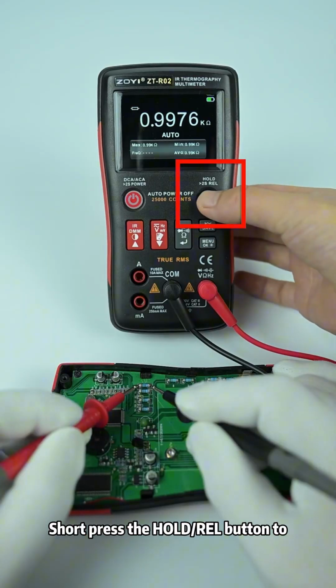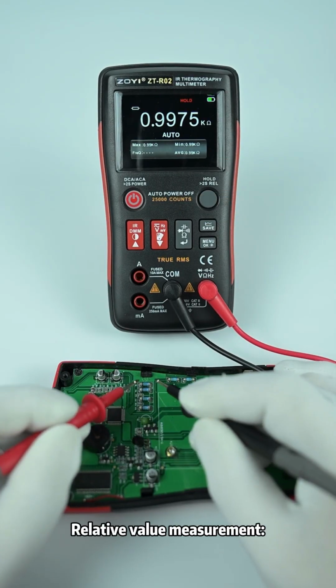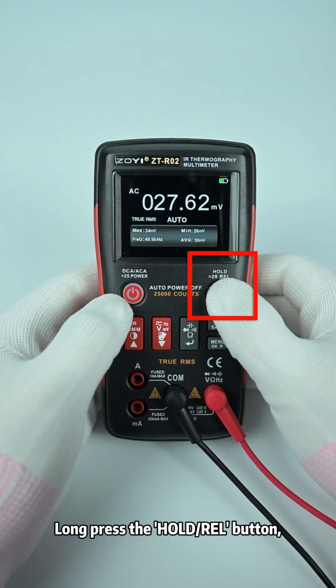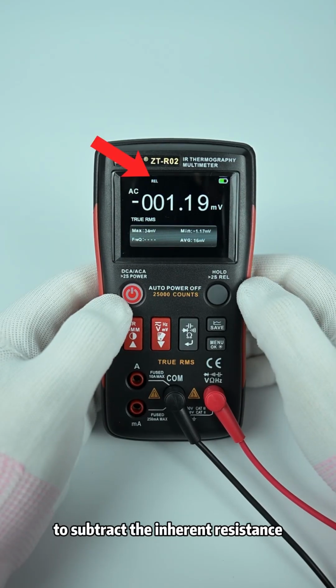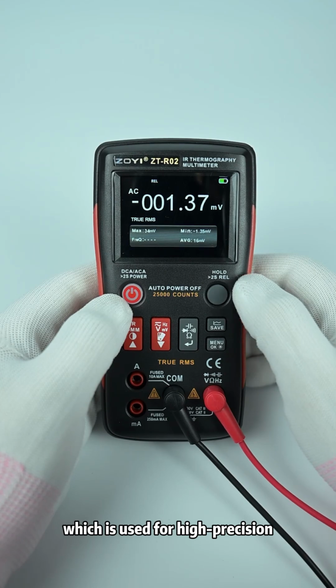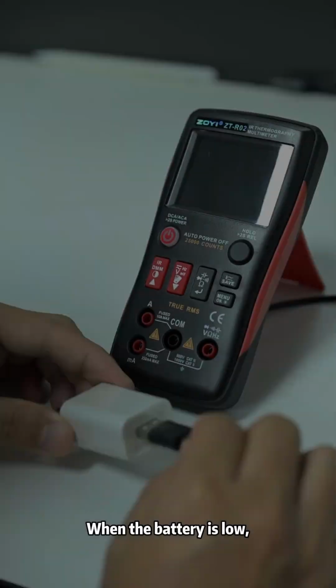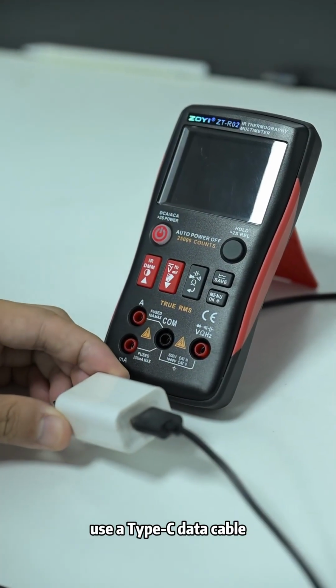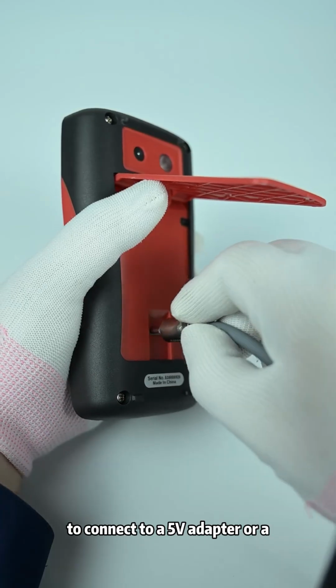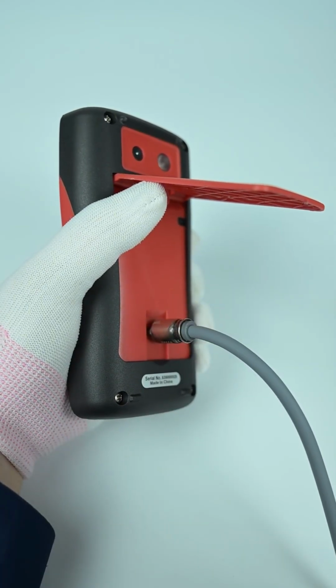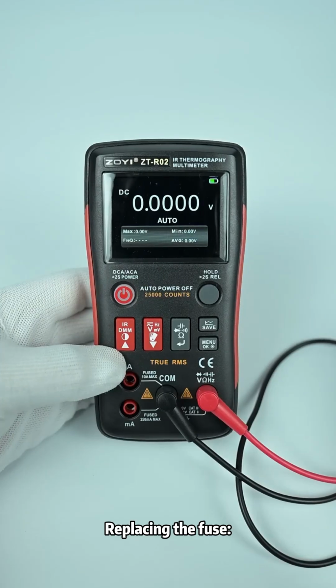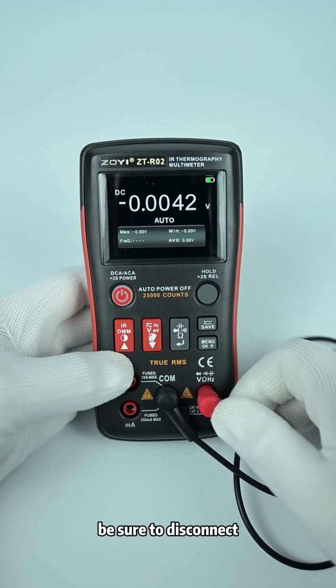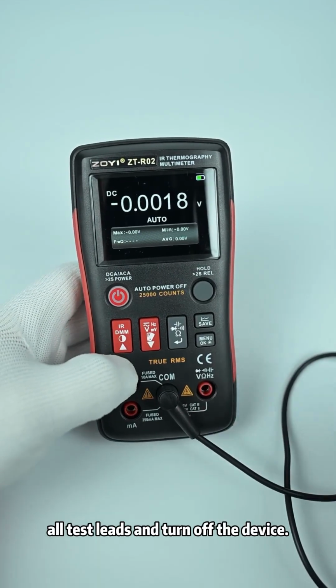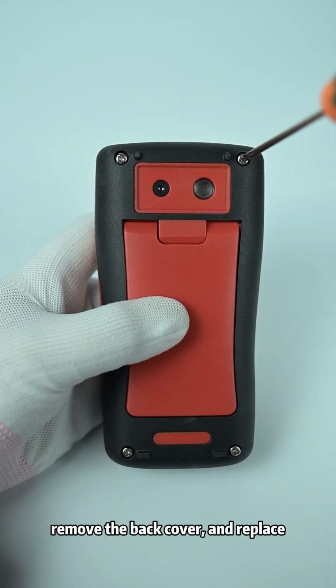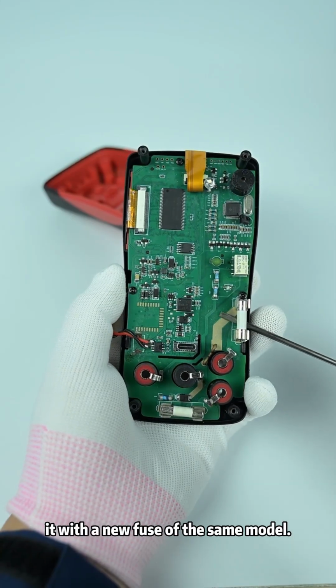Short press the hold/rel button to freeze the reading. Relative value measurement. Long press the hold/rel button to subtract the inherent resistance of the probe wires, which is used for high precision low resistance measurements. When the battery is low, use a Type-C data cable to connect to a 5-volt adapter or a computer USB port to charge the device. Fuse replacement. Before replacement, be sure to disconnect all test leads and turn off the device. Unscrew the back cover screws, remove the back cover, and replace it with a new fuse of the same model.